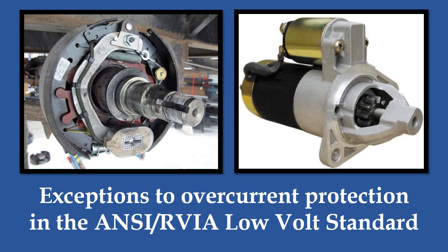There are some exceptions to be noted concerning overcurrent protection in the low voltage system. First, any braking circuits for trailers and any cranking circuits, such as engine starters, are not covered by the ANSI RVIA low volt standard. The protection of these circuits still remains the responsibility of the RV manufacturer based on federal and state motor vehicle safety standards. These two items do fall outside the RVIA inspection program and the low voltage standard.